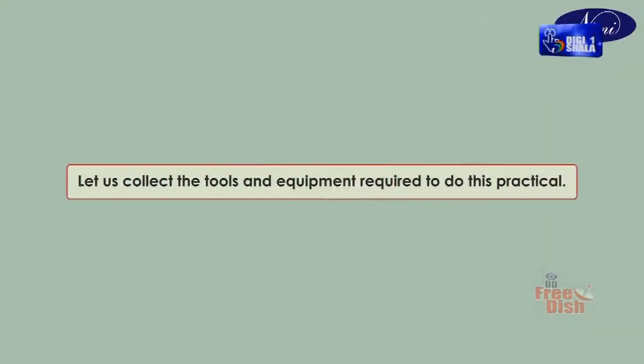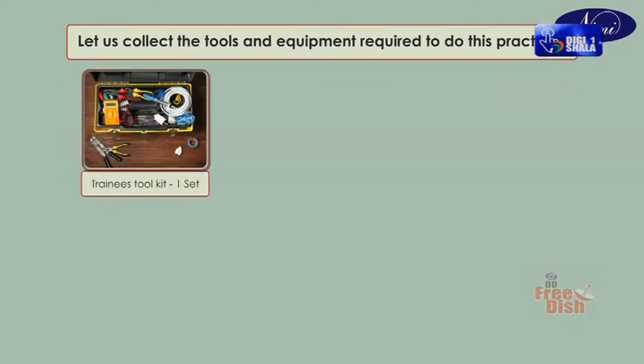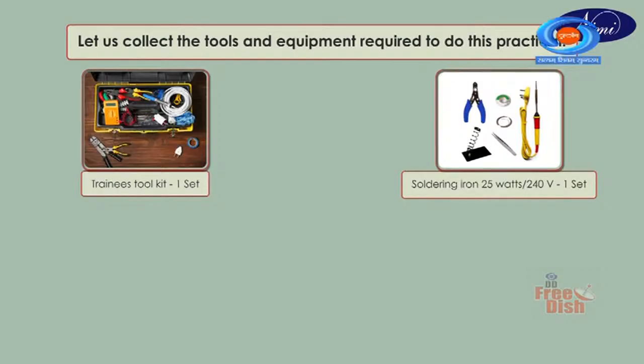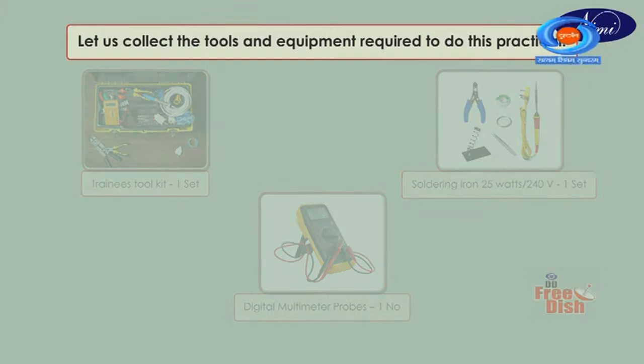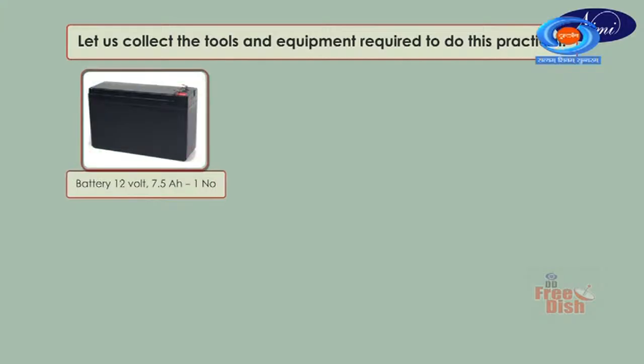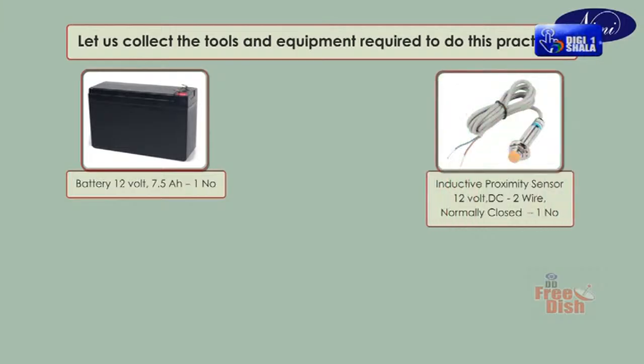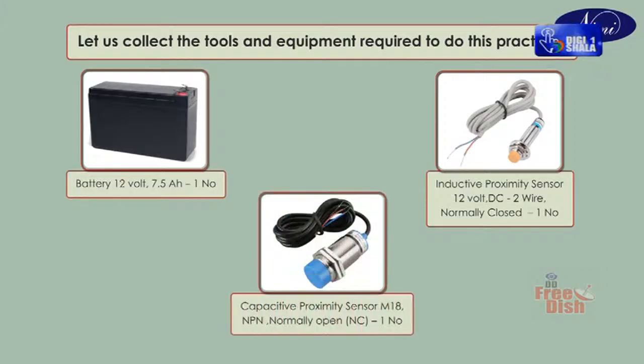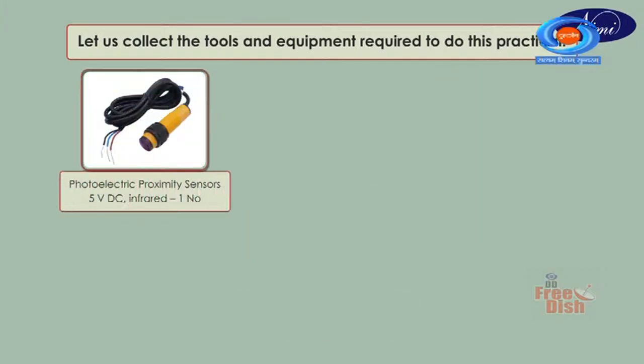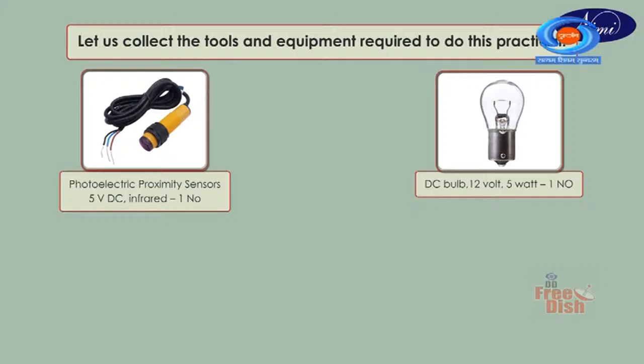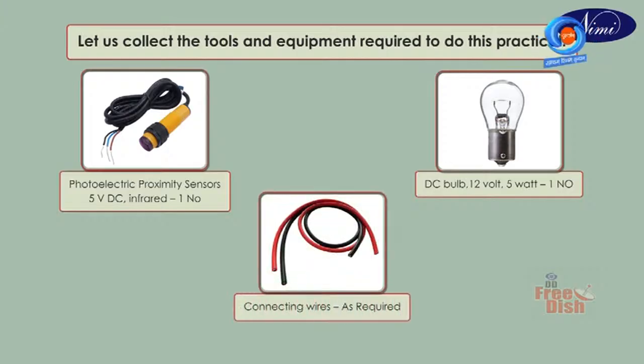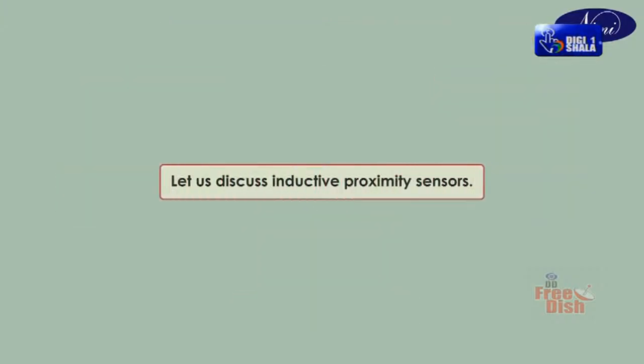Let us collect the tools and equipment required to do this practical. Trainee's toolkit, 1 set. Soldering iron 25 watts by 240 volt, 1 set. Digital multimeter probes, 1 number. Battery 12 volt 7.5 Ah, 1 number. Inductive proximity sensor 12 volt DC 2 wire normally closed, 1 number. Capacitive proximity sensor M18 NPN normally open NC, 1 number. Photoelectric proximity sensors 5 VDC infrared, 1 number. DC bulb 12 volt 5 watt, 1 number. Connecting wires as required.